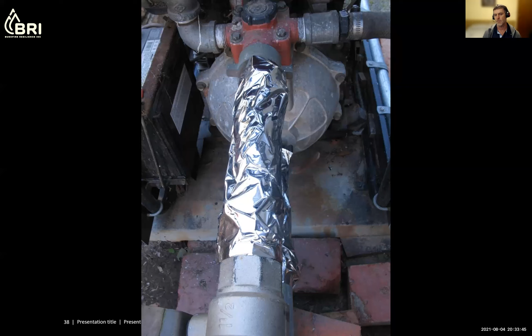So if you have to use certain sections of plastic piping, like in this example, what we really recommend is wrapping it in some type of high-temperature lagging — like an exhaust wrap you get from an automotive shop, a ceramic fibre woven bandage or wrap. That'll prevent embers and heat affecting the plastic too much. Then the ideal finish is to wrap that again with reflective aluminium covering, which repels the radiant heat and gives really good protection for those limited areas where you have to use plastic.